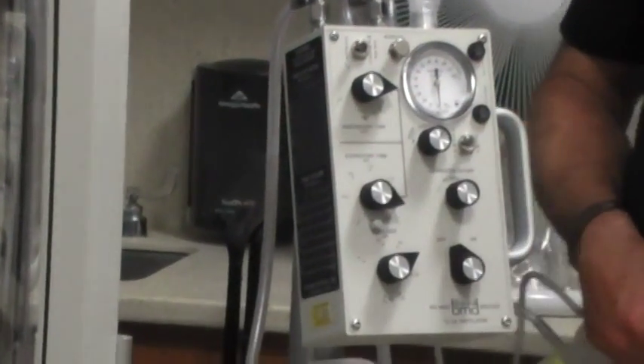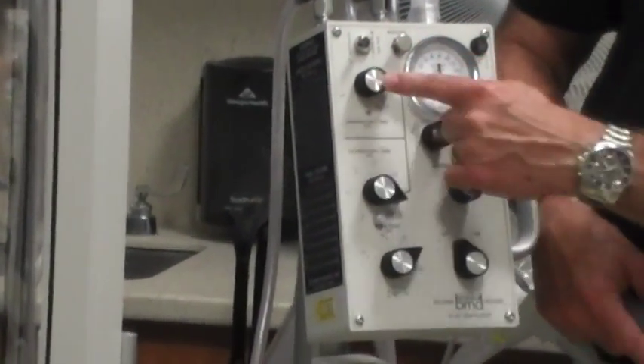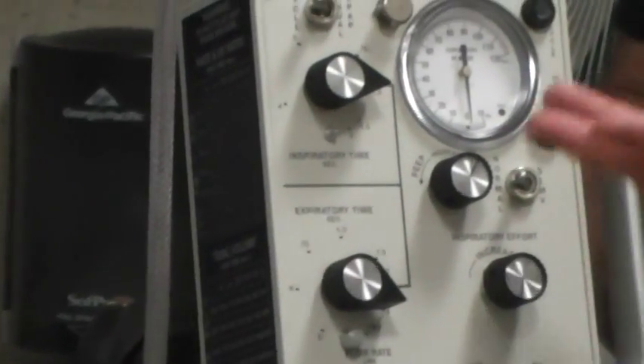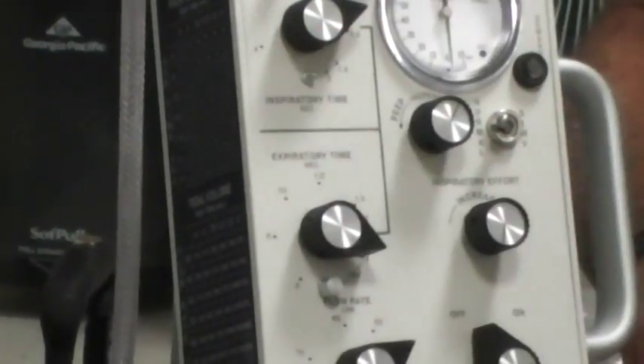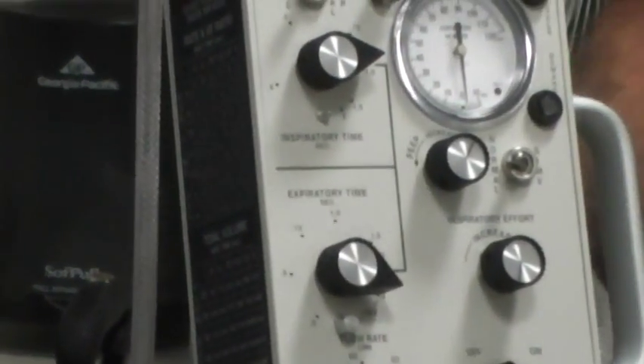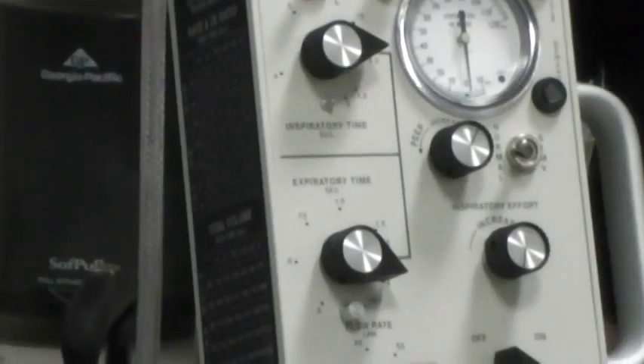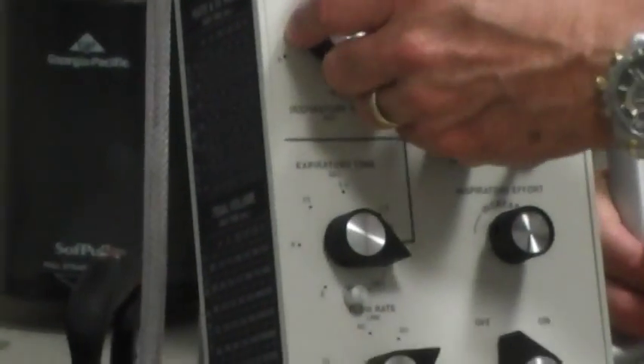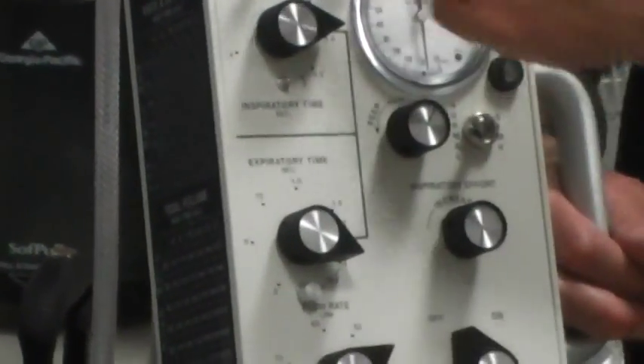So the first knob here is I time. A lot of times we don't really think about I time for adults, but an adult is probably going to be 1 second to 1.5. Just pick one. I usually just choose one. We need to know what we're picking because I'll show you here in a second.